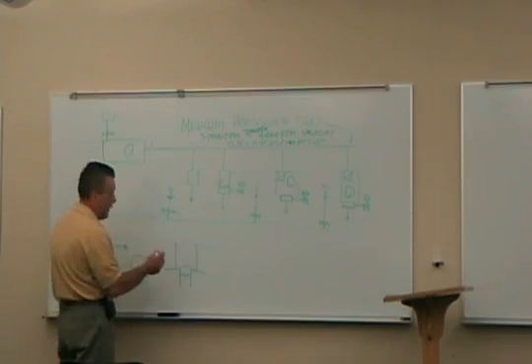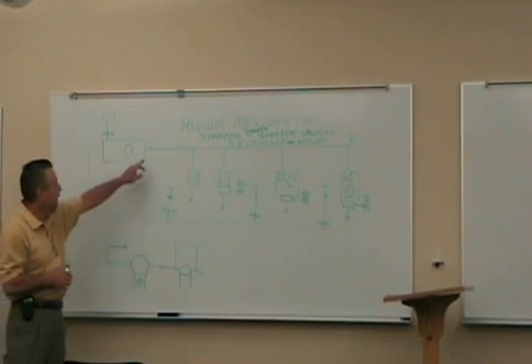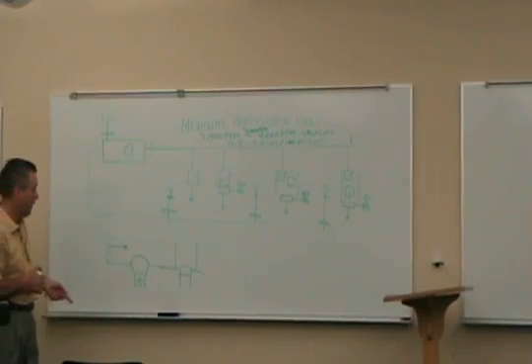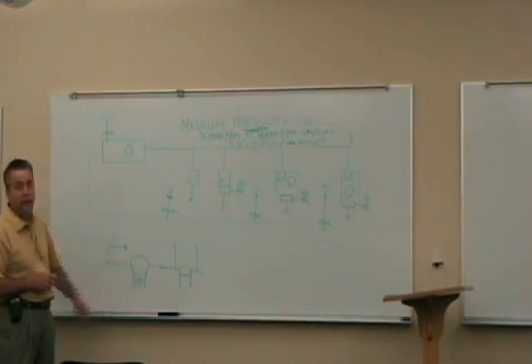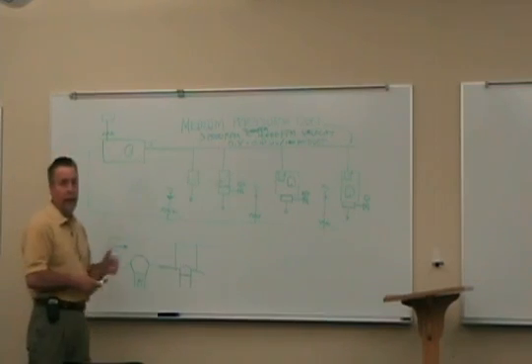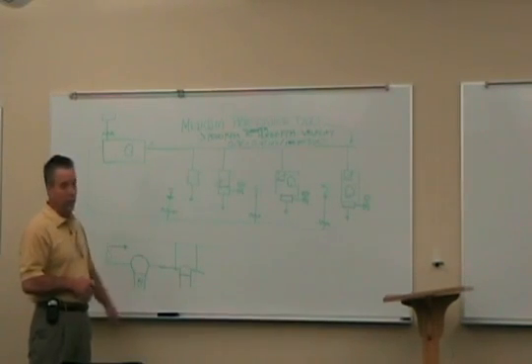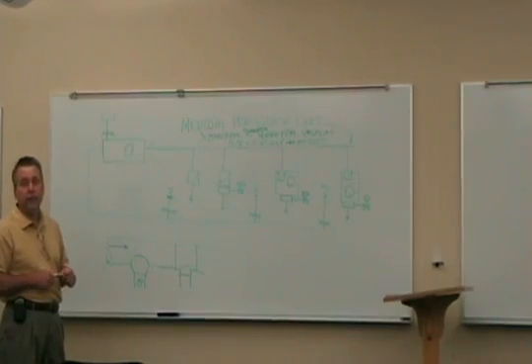And even the square built duct, you can build fittings like this. But in high medium pressure duct, it's very important to use what they call conical fittings or expanded throat fittings to reduce that pressure drop. And that pressure drop may not be very much, but I have seen applications in risers where you've got a riser going down that's maybe at 2,000 feet per minute or 2,500 feet per minute, and a takeoff coming off of this straight tap that might be as high as 1 inch of pressure.